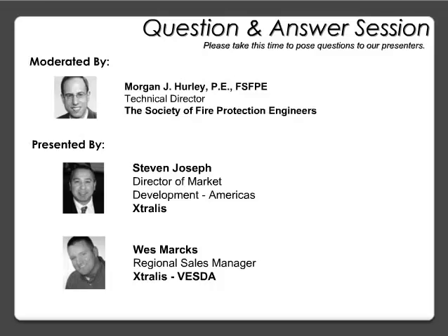Yeah, right. I think Steve covered that in his slide, going through the different categories for standard fire detection, early warning, and very early warning detection, and looking at the spacing coverage requirements. For a standard level of fire detection, you'll be looking at 900 square foot spacing. Early warning, 400 square foot spacing, and 200 square foot spacing for very early warning detection. As far as airflow, it doesn't play into that categorization for an air sampling system, as it's a cumulative system, and for a very early warning application, 200 square foot is really the recommendation.